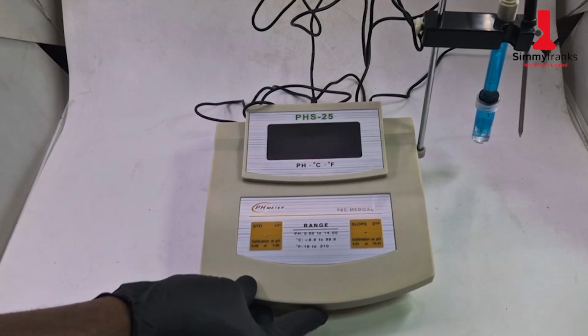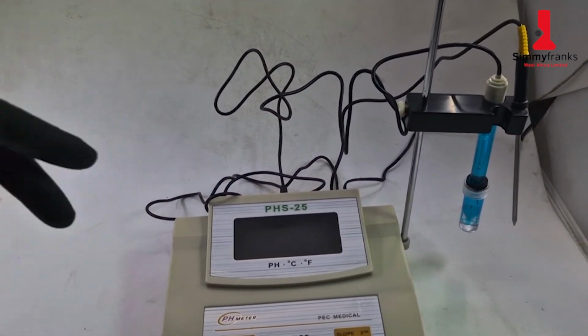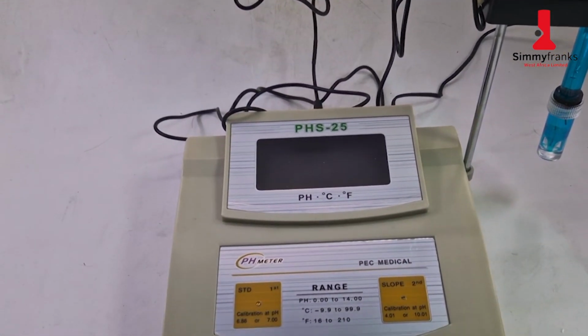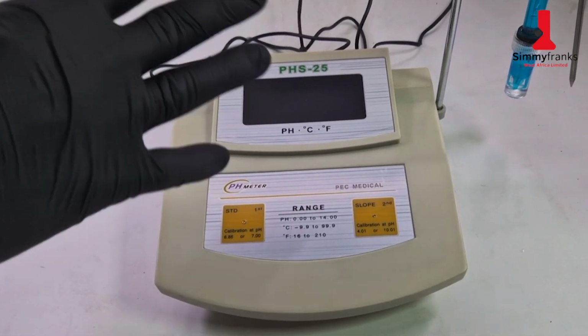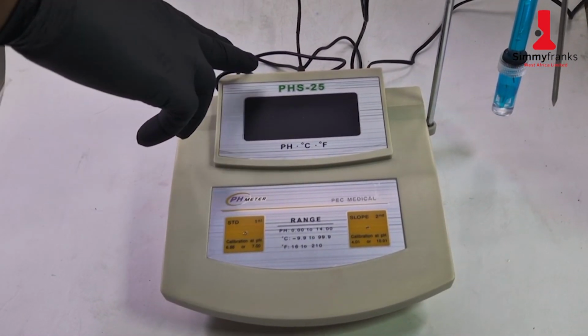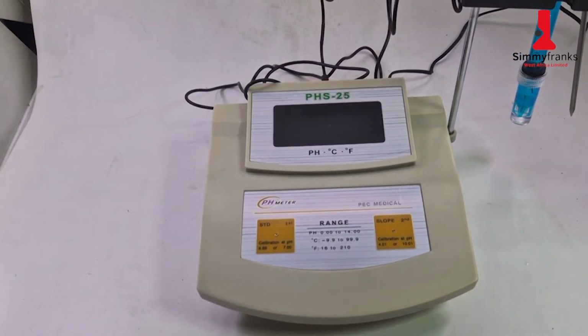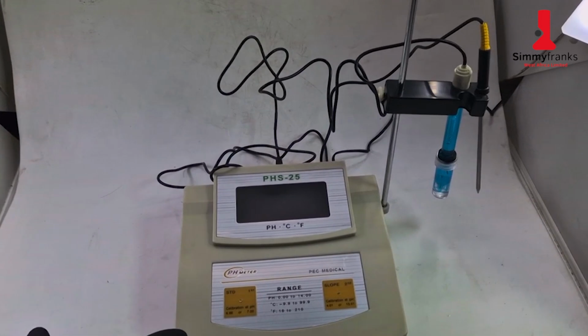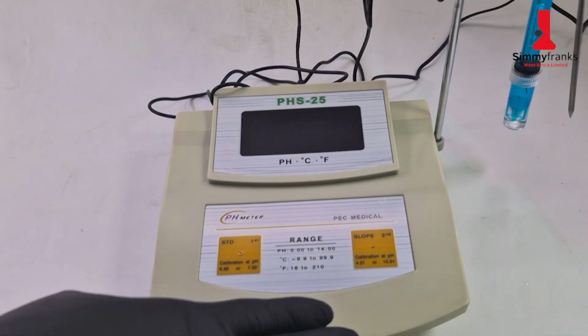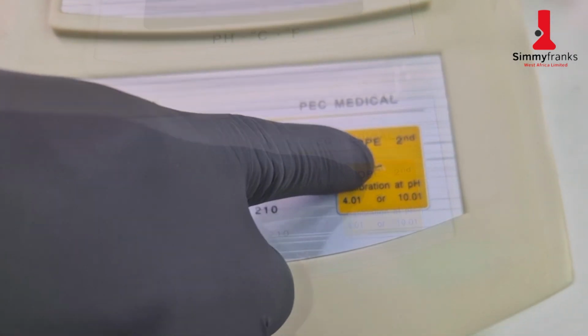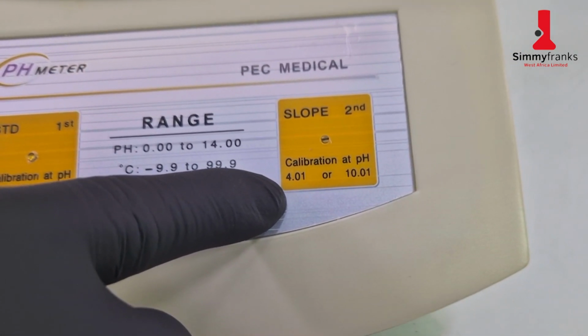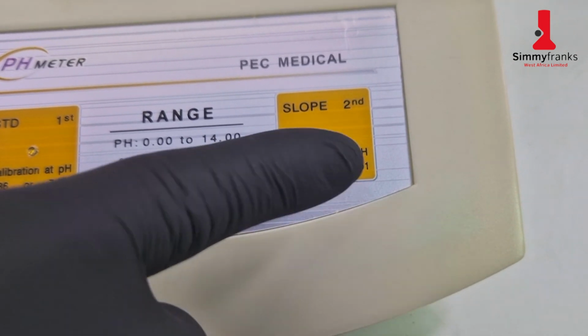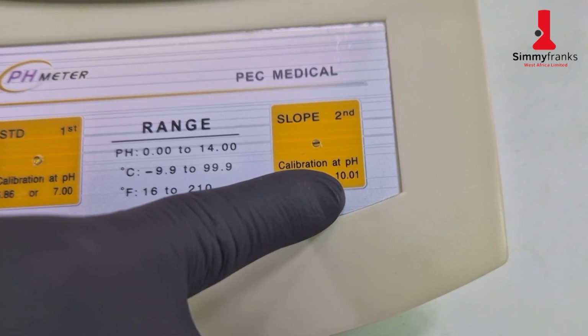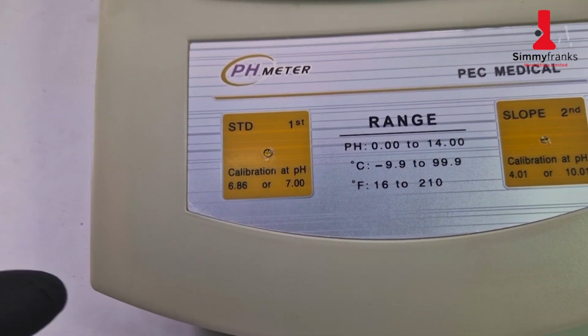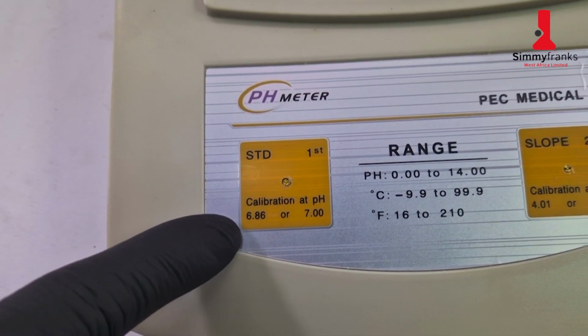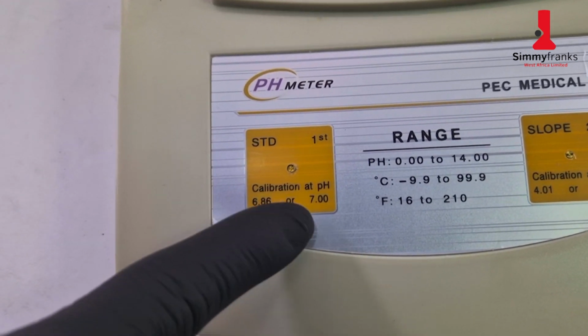So today we are going to be calibrating this tabletop pH meter, and the model is PHS25. There are other pH meters like this, the same format, the same pattern, or it might be PH20, PHS26 or other model, or you can still follow the same procedure for calibrating your pH meter.